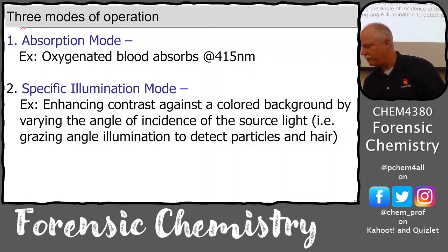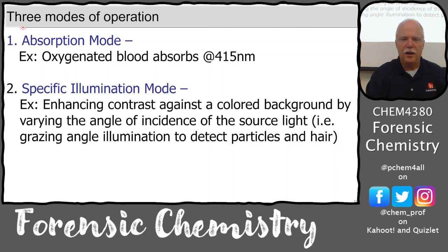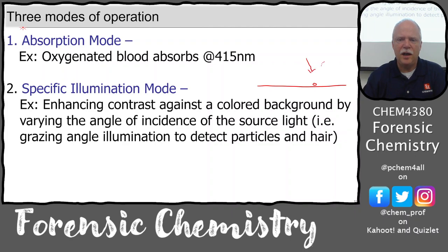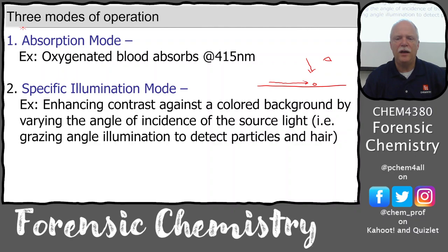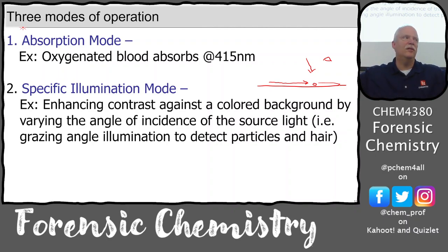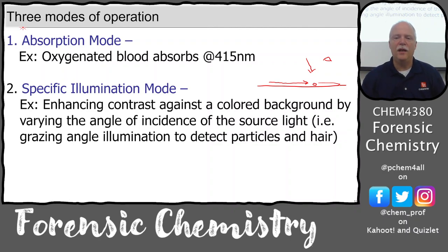If you use a grazing angle to illuminate a surface with a tiny particle or fiber, when the light comes down directly, the particle appears small. But if the light comes at a grazing angle, look at how much shadow the particle casts. Grazing angle is great because you can see the shadows — it can make the particle appear 10 to 100 times larger than it is. You can really detect particles and fibers easily with grazing angle illumination.